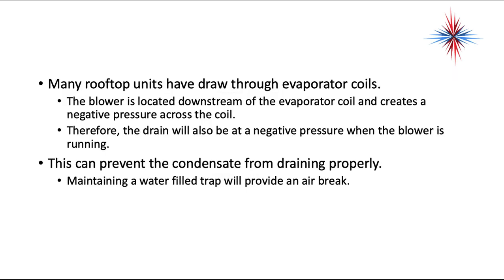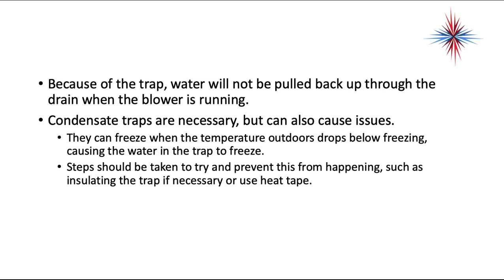Many rooftop units have draw-through evaporator coils. The blower is located downstream of the evaporator coil and creates a negative pressure across the coil. Therefore, the drain will be at a negative pressure when the blower is running. This can prevent the condensate from draining properly. Maintaining a water-filled trap will provide an air break. Because of the trap, water will not be pulled back up through the drain when the blower is running.